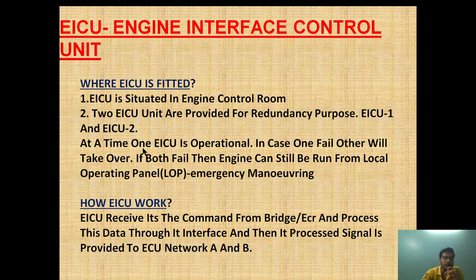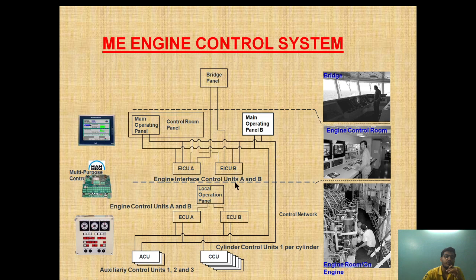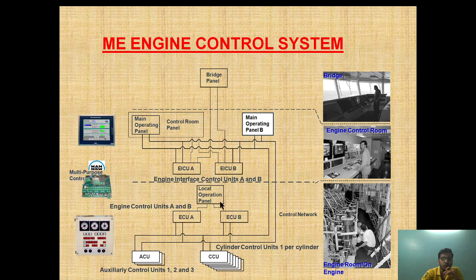At any one time, only one EICU is operational. In case one fails, the other will take over. If both fail, the engine can still be run from the local operating panel via emergency maneuvering — very important. If both EICU A and EICU B fail, control can be taken to the LOP, meaning the local operational panel. Control transfers from the engine control room to the emergency maneuvering platform, and from there commands can still be given to ECU A and ECU B.